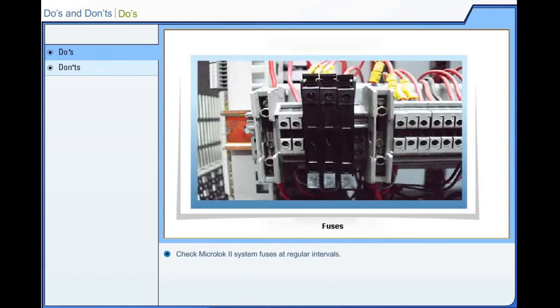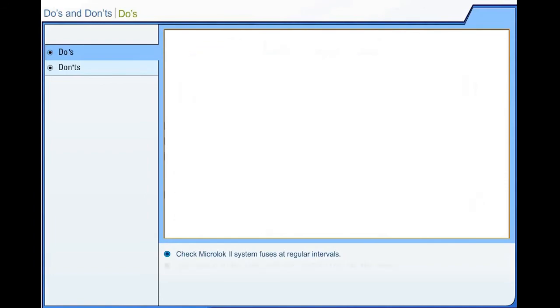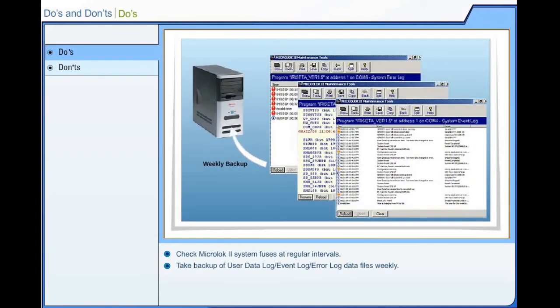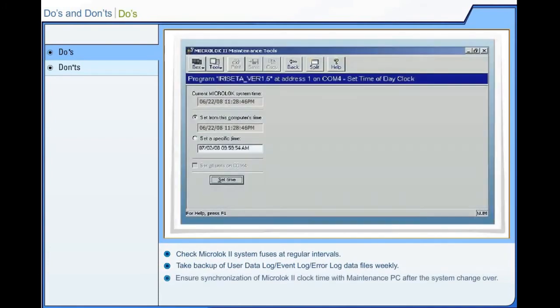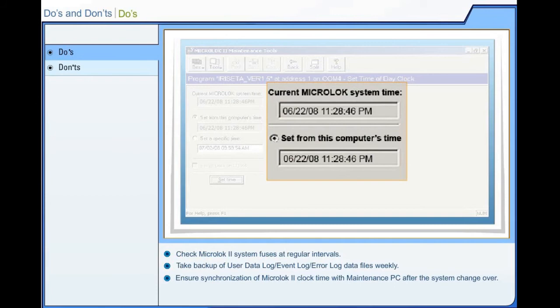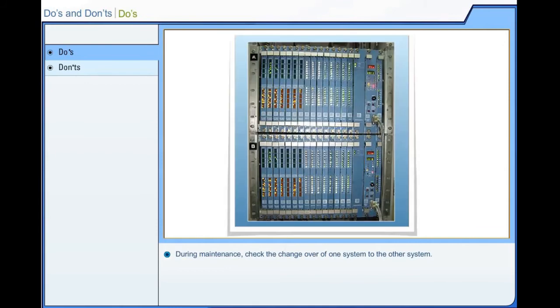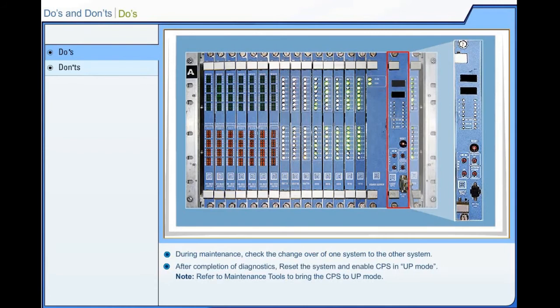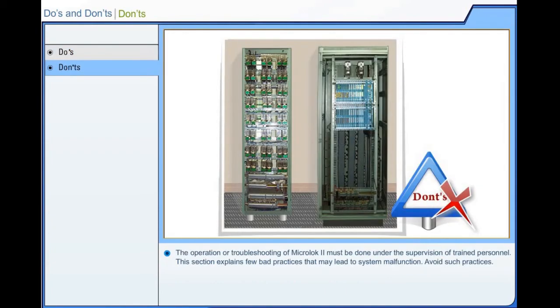Check Microlok II system fuses at regular intervals. Take backup of user data log, event log, or error log data files weekly. Ensure synchronization of the Microlok II clock time with the maintenance PC after the system changeover. During maintenance, check the changeover of one system to the other system. After completion of diagnostics, reset the system and enable conditional power supply in UP mode. Refer to Maintenance Tools to bring the CPS to UP mode. The operation or troubleshooting of Microlok II must be done under the supervision of trained personnel.